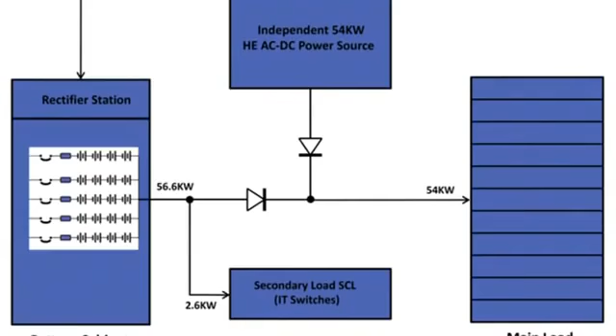In our case, you do the same thing from the utility, but you distribute it straight to the rack. You do not have that energy transformation at a UPS or at the PDU level. You get very efficient energy to the actual server. The server itself then takes that energy and makes useful work out of it.